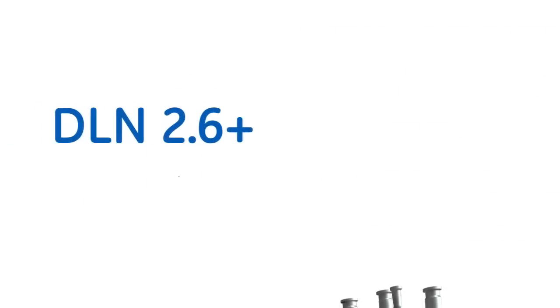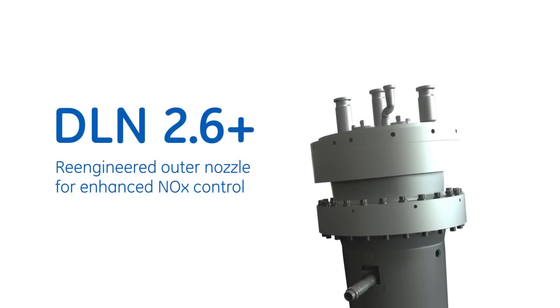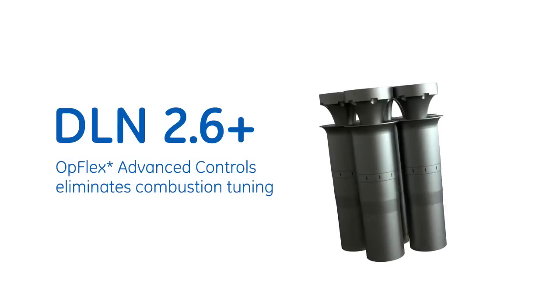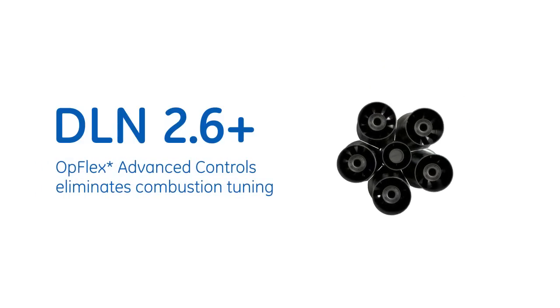The DLN 2.6 Plus features a central premix nozzle and five outer nozzles which have been re-engineered, adding a fuel passage upstream of the nozzle and swirler, and eliminating the diffusion passage.